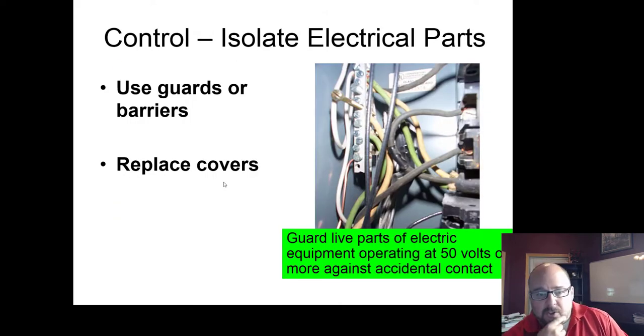So what you see here on the screen looks like the neutral bar, and on the right you're seeing this portion of the switches. The hot lines get connected here, and the hot bus is right behind it. But the neutral line — there's a weird looking screw there that shouldn't be there, and you see a few grounds in there as well. This is kind of a mess.